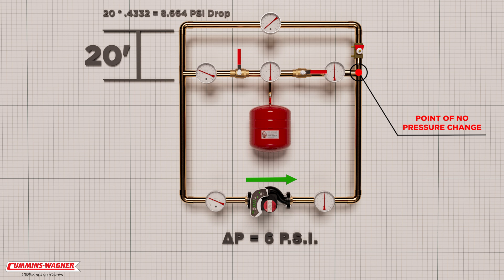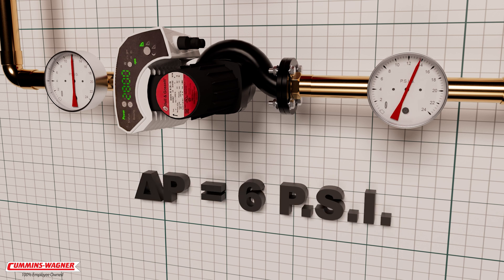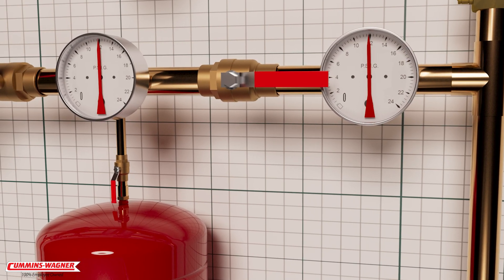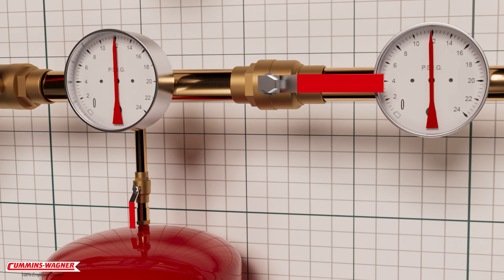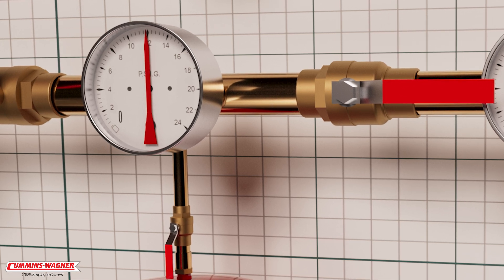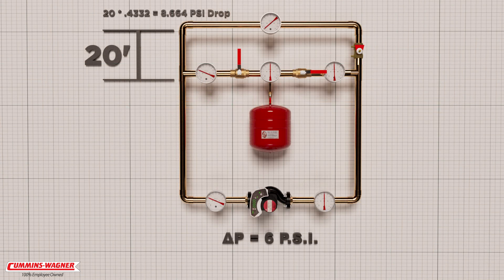We can see the immediate result of pumping into the point of no pressure change. Previously, with the expansion tank in the correct position, we were able to achieve 18 psi on the discharge of the circulator. But now that we're pumping into the point of no pressure change, we can only achieve the pressure at that point. Since the expansion tank is charged to match the system pressure — in this case 12 psi — the circulator is unable to increase the pressure beyond 12 psi, so our discharge pressure at the circulator is 12 psi.